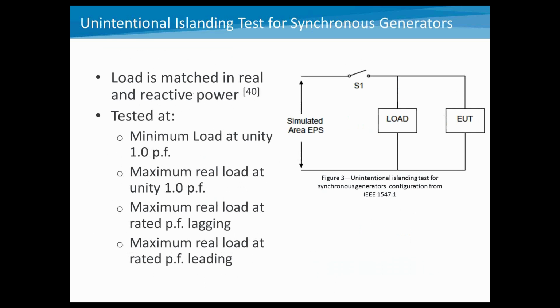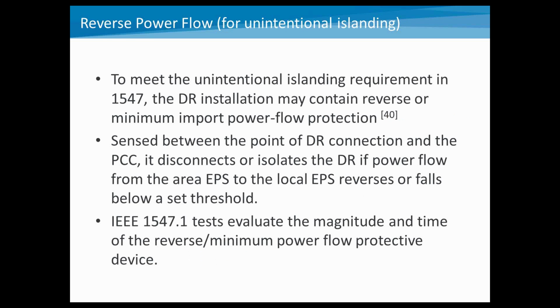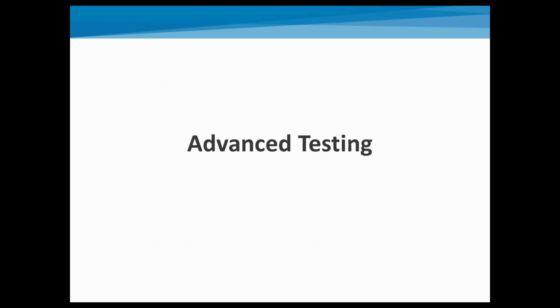As we look at a couple other tests inside of 1547.1, there's one for synchronous generators. Again, the key here is to match real and reactive power and then get zero current flow across switch S1, and open that up. For synchronous generators, this is done at things like minimum load at unity power factor, maximum load at unity power factor, real load at rated power factor, leading and lagging, so a variety of conditions. And then there's also a test in there for understanding reverse power flow. So for example, if you have reverse power flow protection in the case of relays, you're able to set up and test and evaluate those. Again, these are the standardized tests in 1547, developed over a number of years and used successfully for quite a few years. And those are also integrated into UL 1741 for actual certification processes.